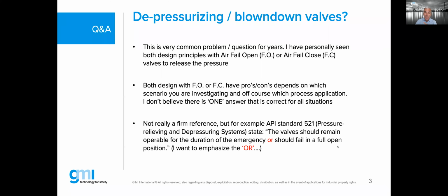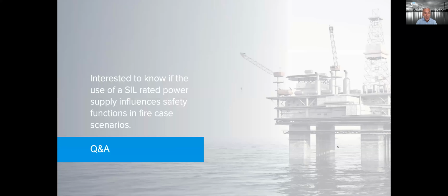That's actually applicable for both the air-to-close or the air-to-open. However, they also throw an "or" in there. And because of the "or", that's where the discussion will be starting. It should fail in a full open position. And that's something that you have to think about. So unfortunately, I cannot give you a clear black and white answer, but I try to give you a little bit of items to think about. And again, API 521 may give you a little bit more guidance than I can do here in a functional safety webinar. All right, Andrea.